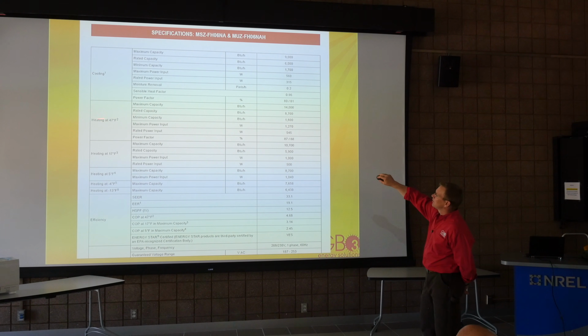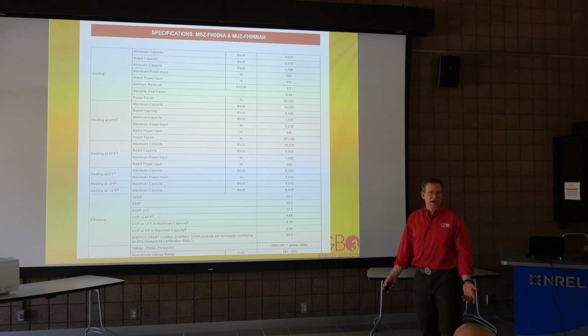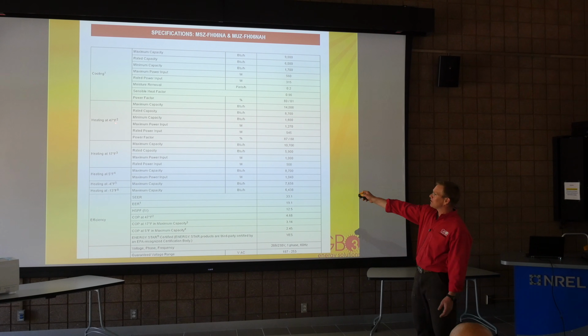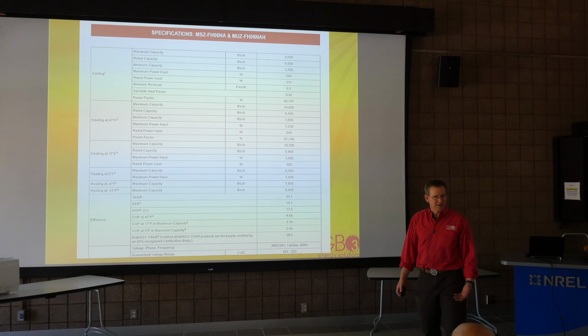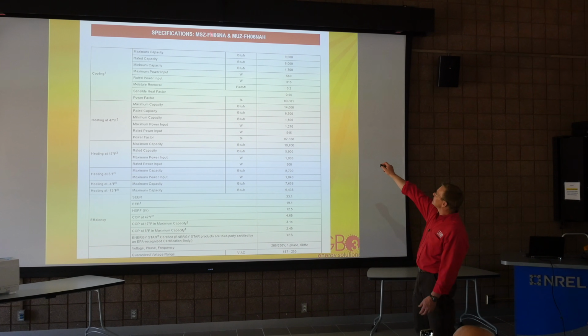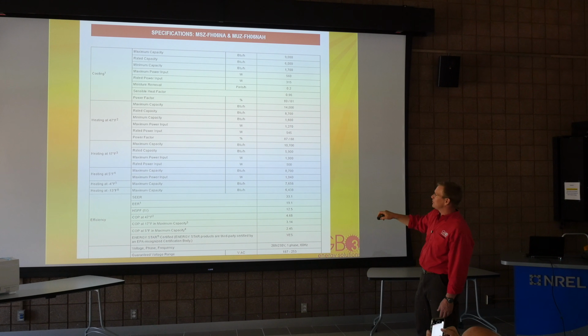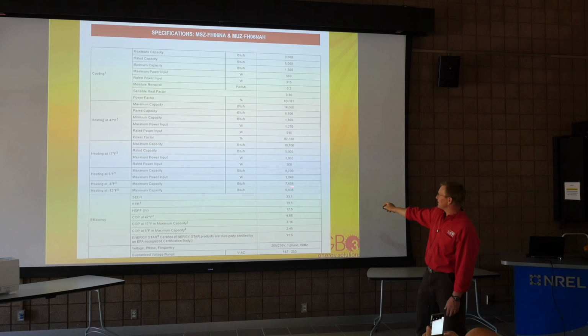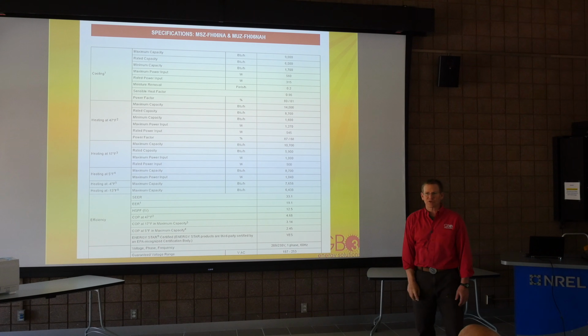You'll notice heating at 47, it has a certain capacity in BTUs - that's how many BTUs this thing can put out at 47. When we dropped to 17, the output dropped. Not surprising - there's less heat in 17-degree air than in 47-degree air. But this is a 06, a 6,000 BTU unit. They're giving me my capacity of greater than 6,000 all the way down to minus 13.